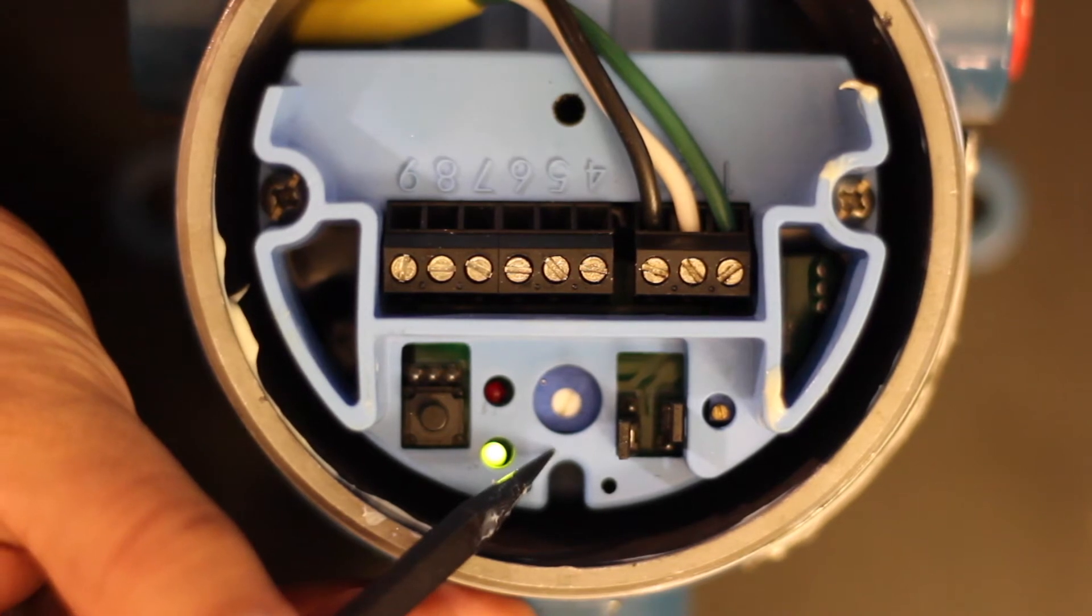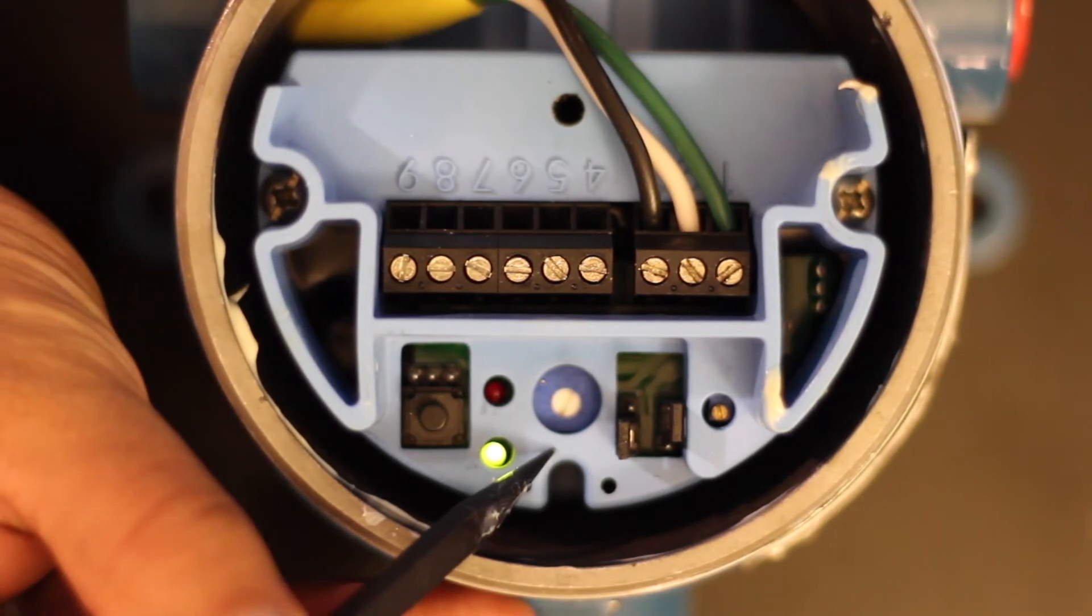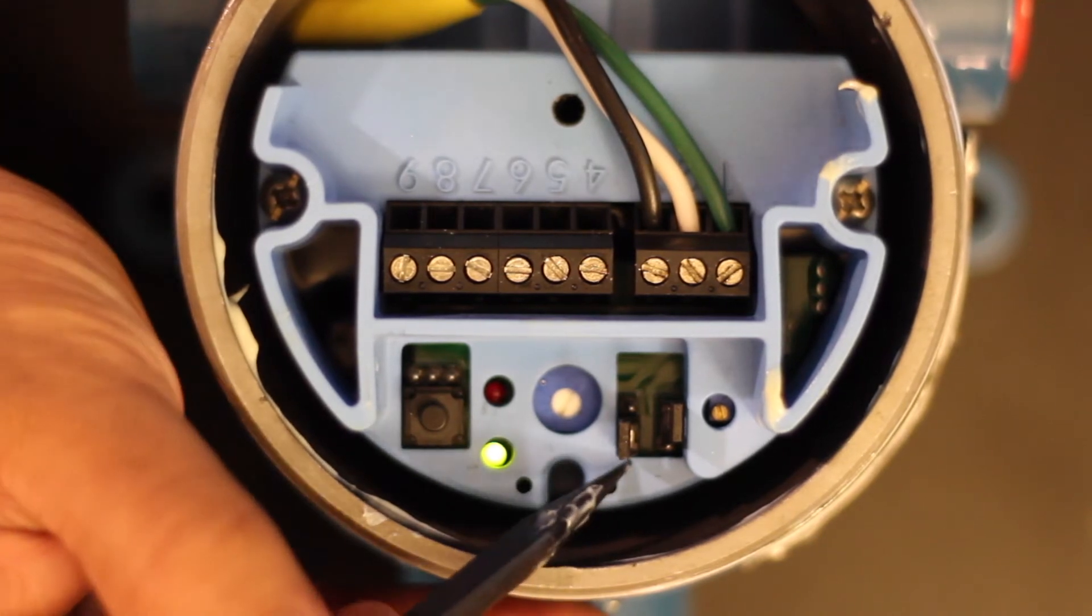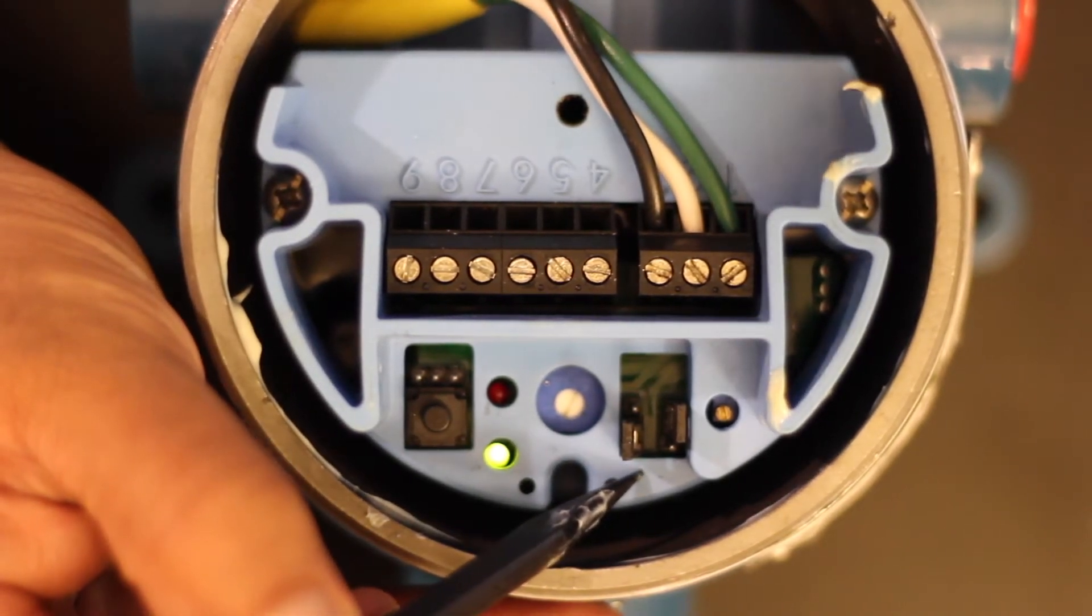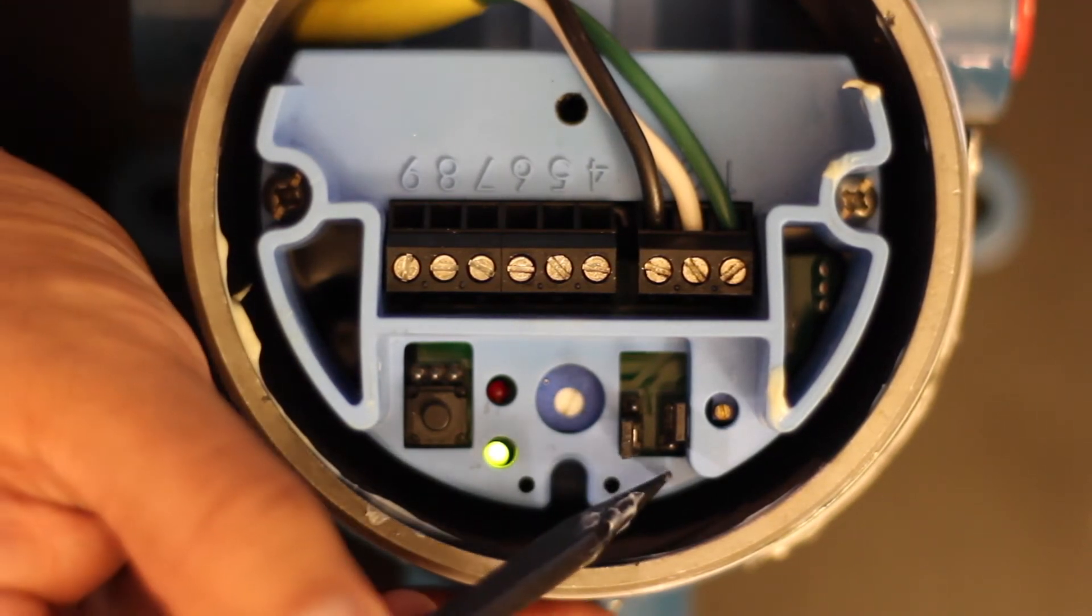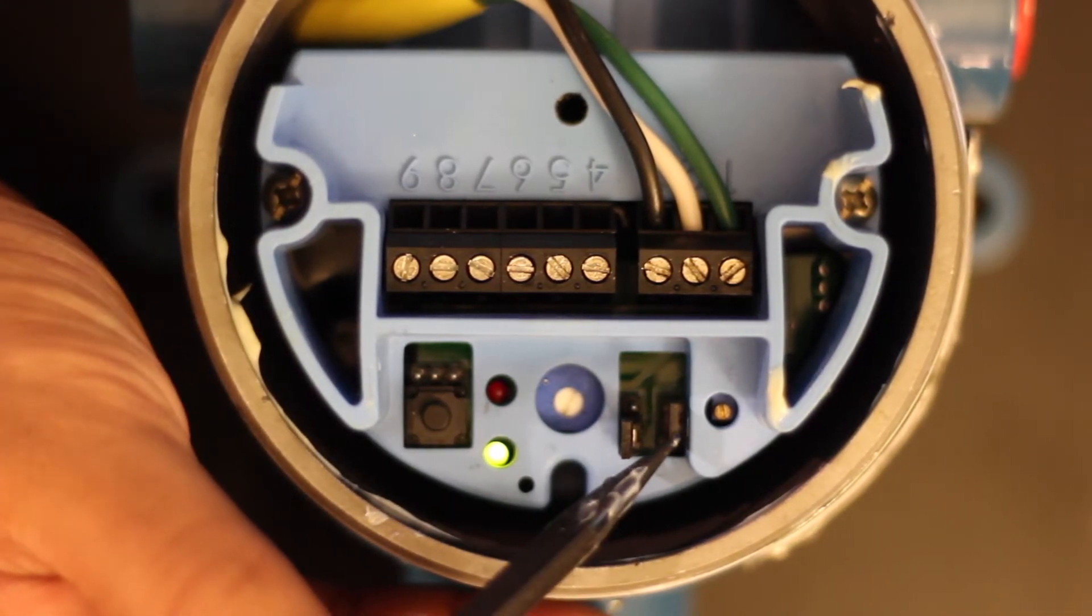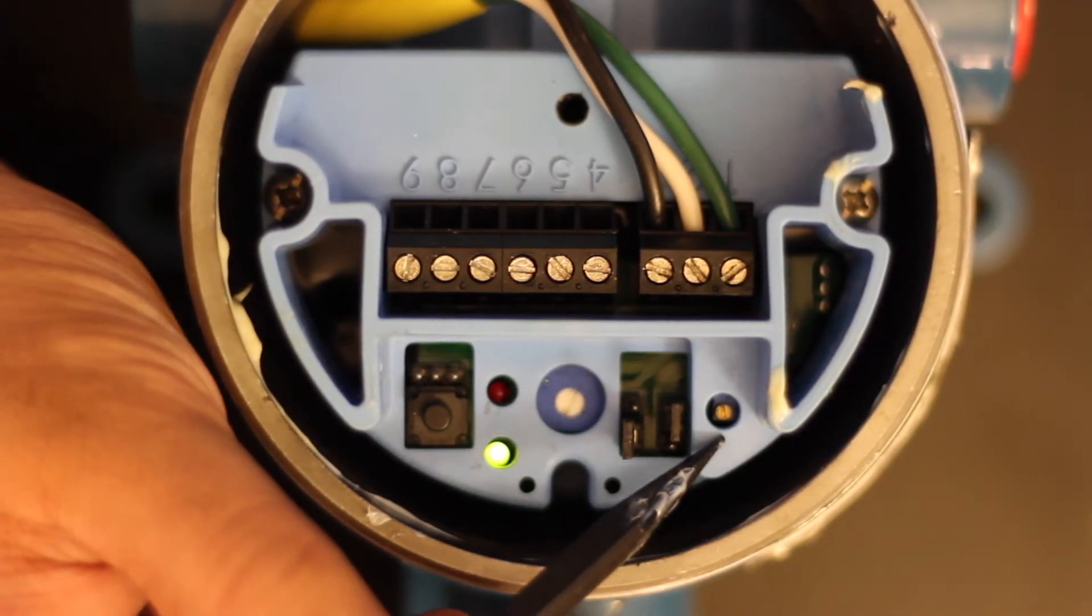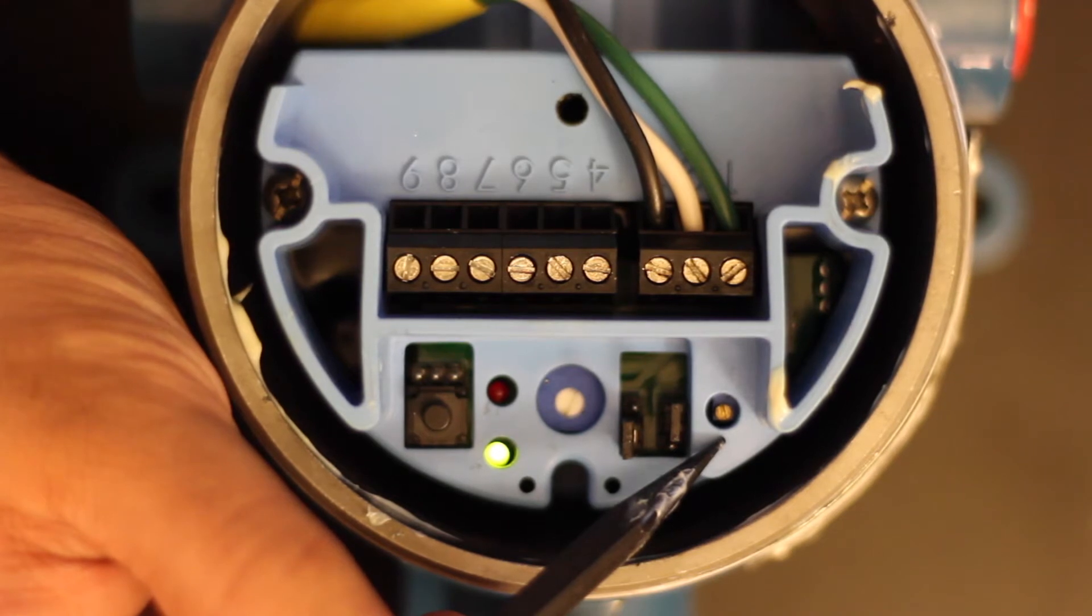In the middle we have a 0 to 60 second, 270 degree time delay pot. Moving over, we have our fail safe jumper to indicate high level or low level fail safe. Next up, you have your time delay jumper. This is for forward or reverse acting time delay. And lastly, if you are in manual calibration, this is your manual calibration adjustment pot.